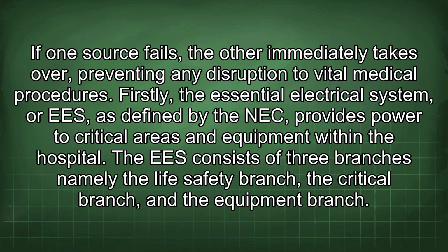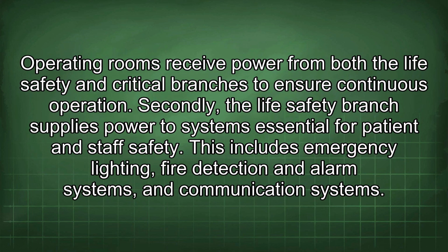Firstly, the Essential Electrical System, or EES, as defined by the NEC, provides power to critical areas and equipment within the hospital. The EES consists of three branches, namely the Life Safety Branch, the Critical Branch, and the Equipment Branch. Operating rooms receive power from both the life safety and critical branches to ensure continuous operation.